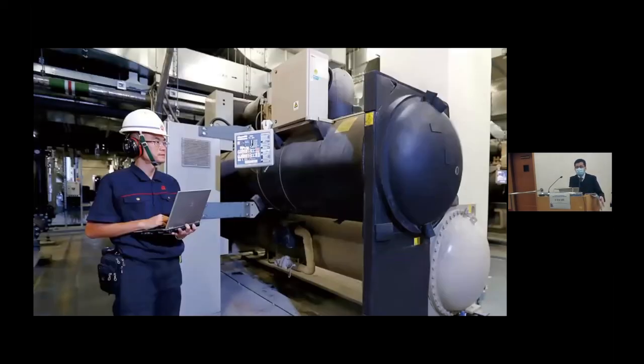One might ask, how do I go about improving my ventilation if I'm not an engineer? So my advice is first, appoint a ventilation specialist to review your ventilation design and settings. As in the case of the fitness center I just mentioned, proper equipment was installed. However, the settings might be off. For other cases, there might be a need to install additional fans and equipment in order to achieve the desired airflow results. But this is not the end of the equation.